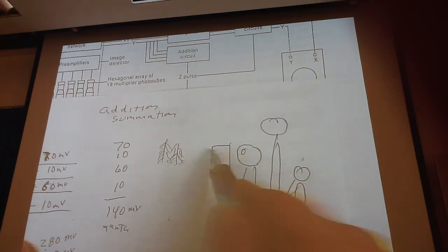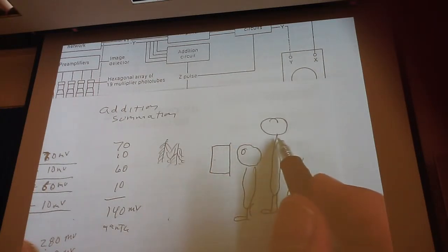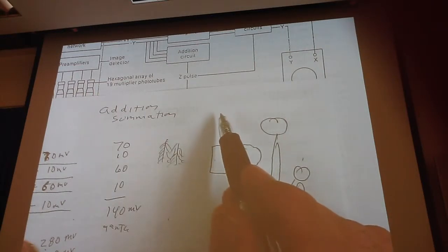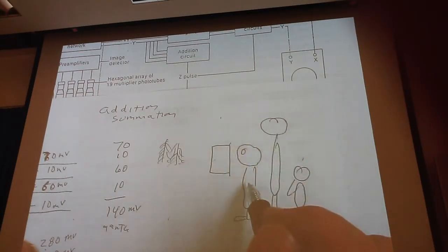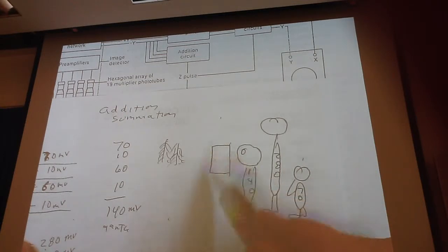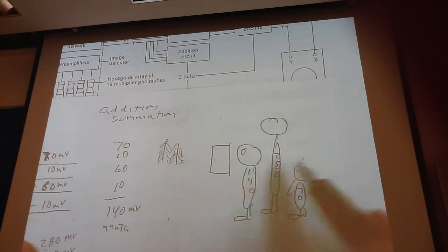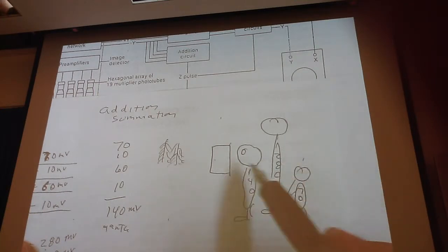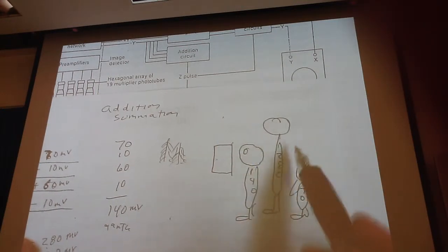Obviously you can't look out that window, can you? So you have to have an ability to adjust this window so that you can look up here or go down here. If you imagine that this is my 140 keV and this is my 280 keV and this is my 70 keV, this is one of the things that you do when you change photon energies or change radionuclides.